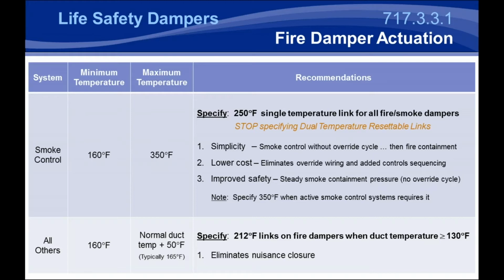to pressurize certain areas. So if it's a non-affected area, say if you've got a 4-story building and there's a fire on the 2nd story, the 1st, 3rd, and 4th stories would be pressurized to keep smoke from getting in by keeping the supply open and shutting off the return, while, say, the fire affected area on the 2nd floor would have the return shut off and the exhaust open. The supply shut off and the exhaust open, to allow for some smoke evacuation out of the building.